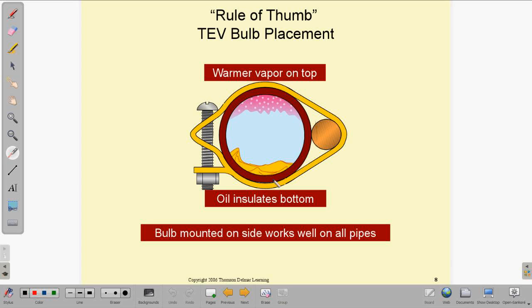And then there's oil on the bottom, and that insulates the sensing bulb from responding quickly to the temperatures, because that oil has to heat up, and if it flows from a cooler place down here to the bottom, it's always going to be changing temperature. So it's a good idea to keep it at 3 and 9 o'clock if you can do it. Okay, so that works well in all size pipes. So when in doubt, mount it at 3 and 9 o'clock.